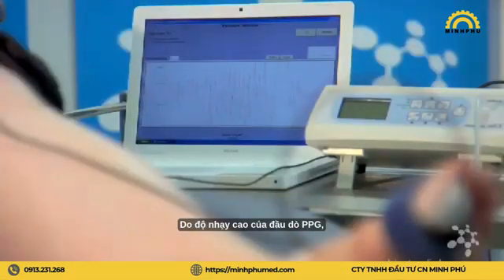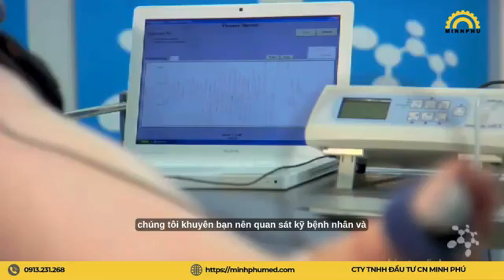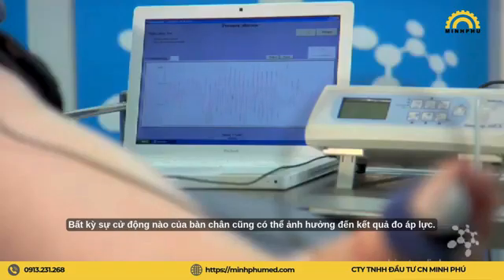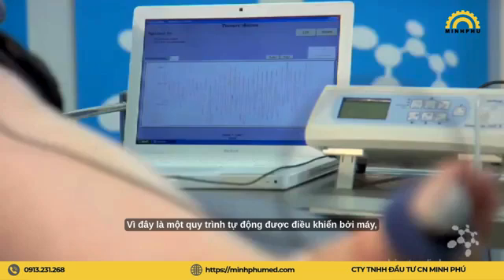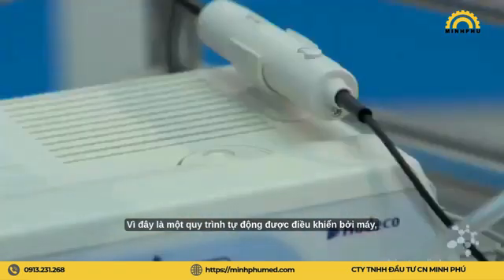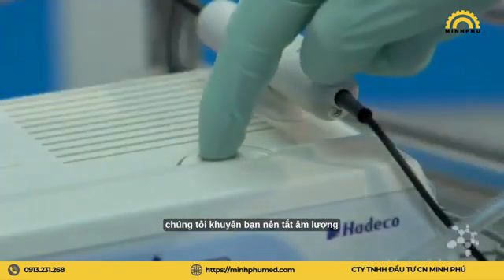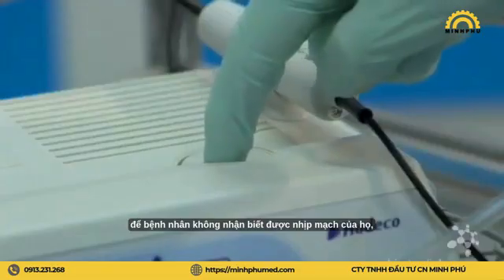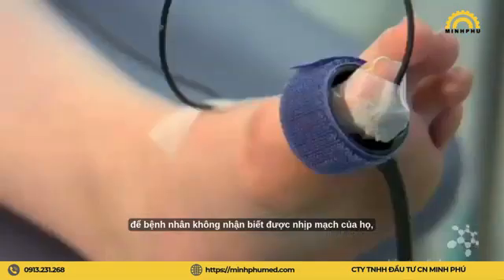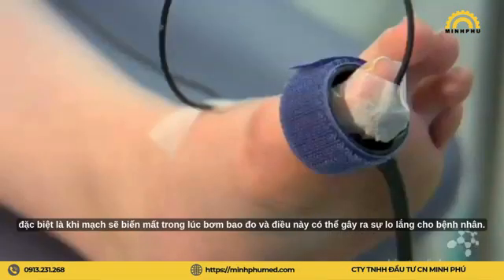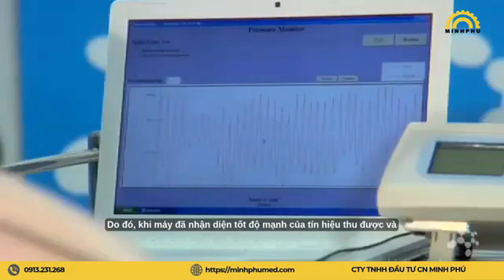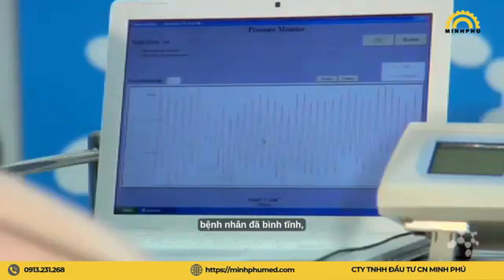Due to the sensitivity of the PPG probe, we suggest that you observe the patient closely and make sure that they remain calm during this brief period. Any movement of the foot can affect the pressure reading. Because this is now an automatic process controlled by the machine, we suggest you turn the sound volume off so that the patient is not aware of their pulse rate, especially as it shall disappear during cuff inflation, and this may cause patient anxiety.